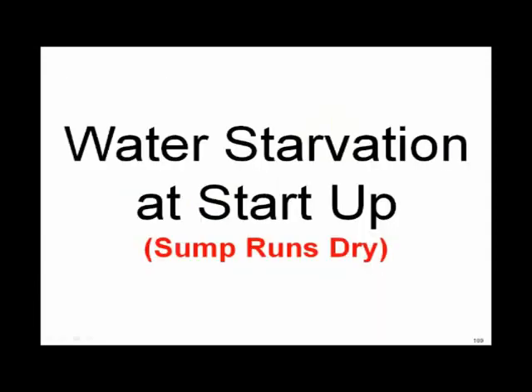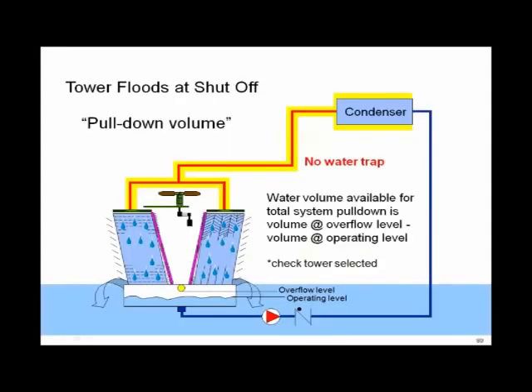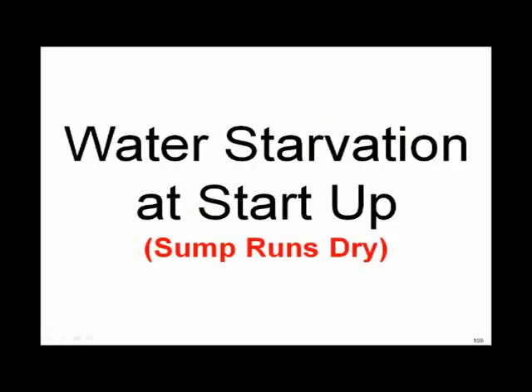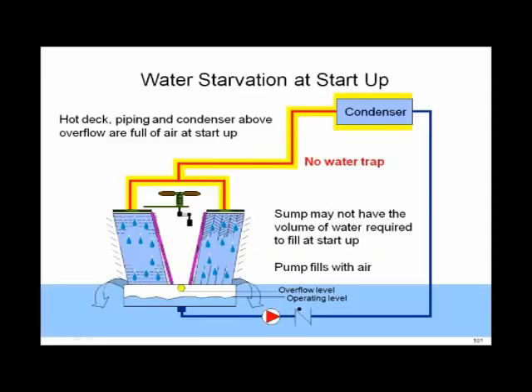Well, what happens when you turn the same pump back on? Remember, we drained all that water out of that piping. We've got to refill the condenser. We've got to refill the condenser water pipe. So when we turn it back on, the sump runs dry, and we don't have enough water to fill the pipe back up, and we cavitate our pump and burn our pump up. Because you pump down the water in the cold water deck of the tower and you pump it completely dry because you don't have enough water.